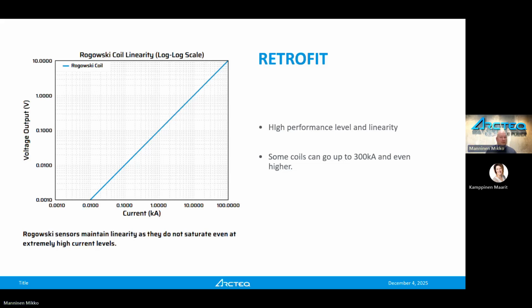And this is absolutely one of the best things with the Rogowski coils. They can easily handle arc flash currents in every application. So for example, this low voltage version, the blue one, if you remember from previous slides, it can go up to 300 kiloamperes, which is quite amazing. So up to 300 kiloamperes without any saturation.